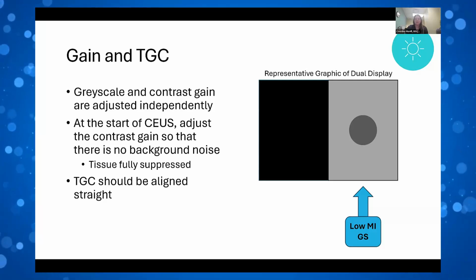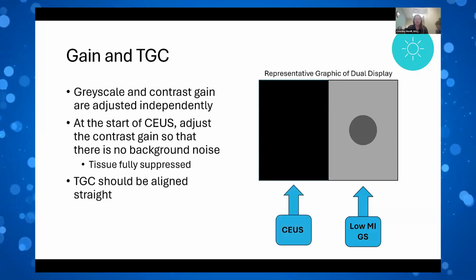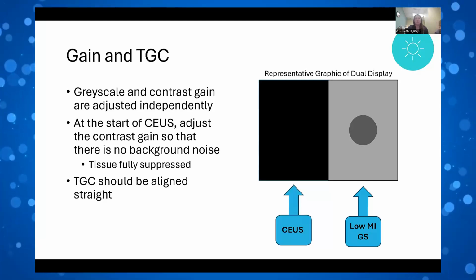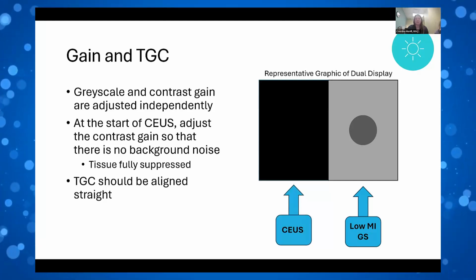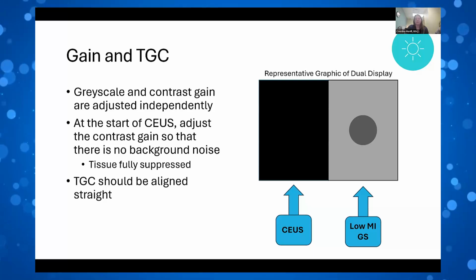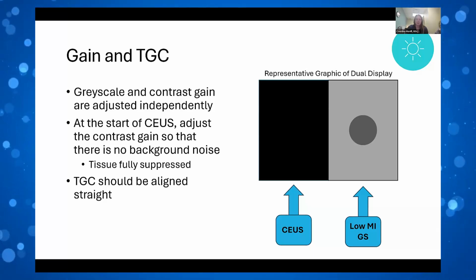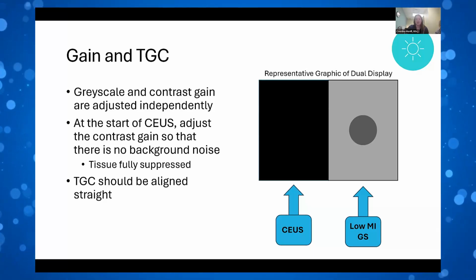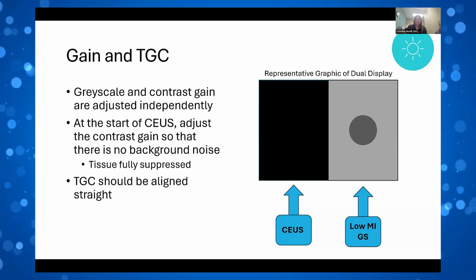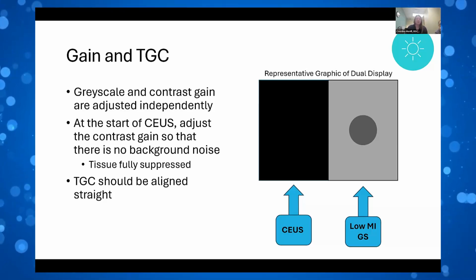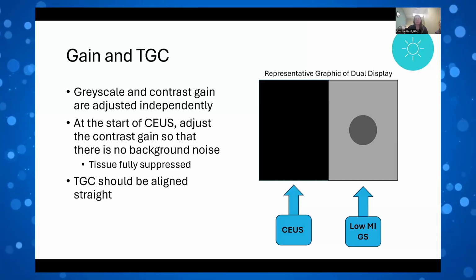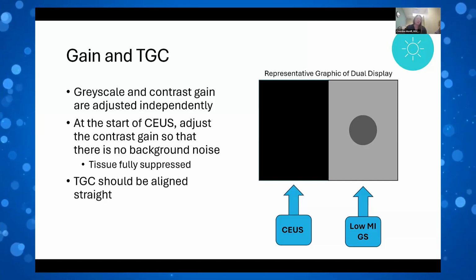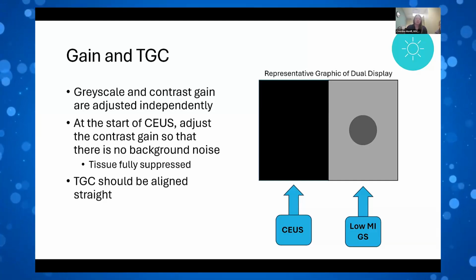At the very start of your CEUS, the left side of your screen, so the CEUS part, should have a full tissue suppression. Because you're subtracting the tissue, you shouldn't have any echoes. But the unfortunate thing about CEUS is that you don't know that your gain setting is appropriate until you put the bubbles in. So how do we solve this problem?